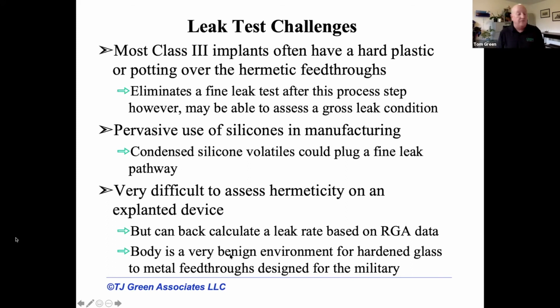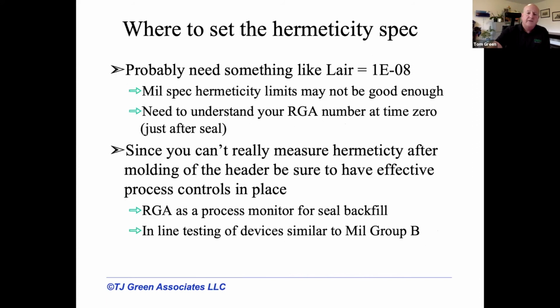And as I mentioned, the body's really pretty benign. Now, maybe a neurostimulator, if you're tugging on the leads. So that's something to keep in mind. And then the question is, where should I set my hermeticity spec? Well, if you just default to the MIL specs, unless you want to comply with Class K space, I don't know that they're going to be good enough. You might want to consider something even tighter than an air leak rate of 1 times 10 to the minus 8.